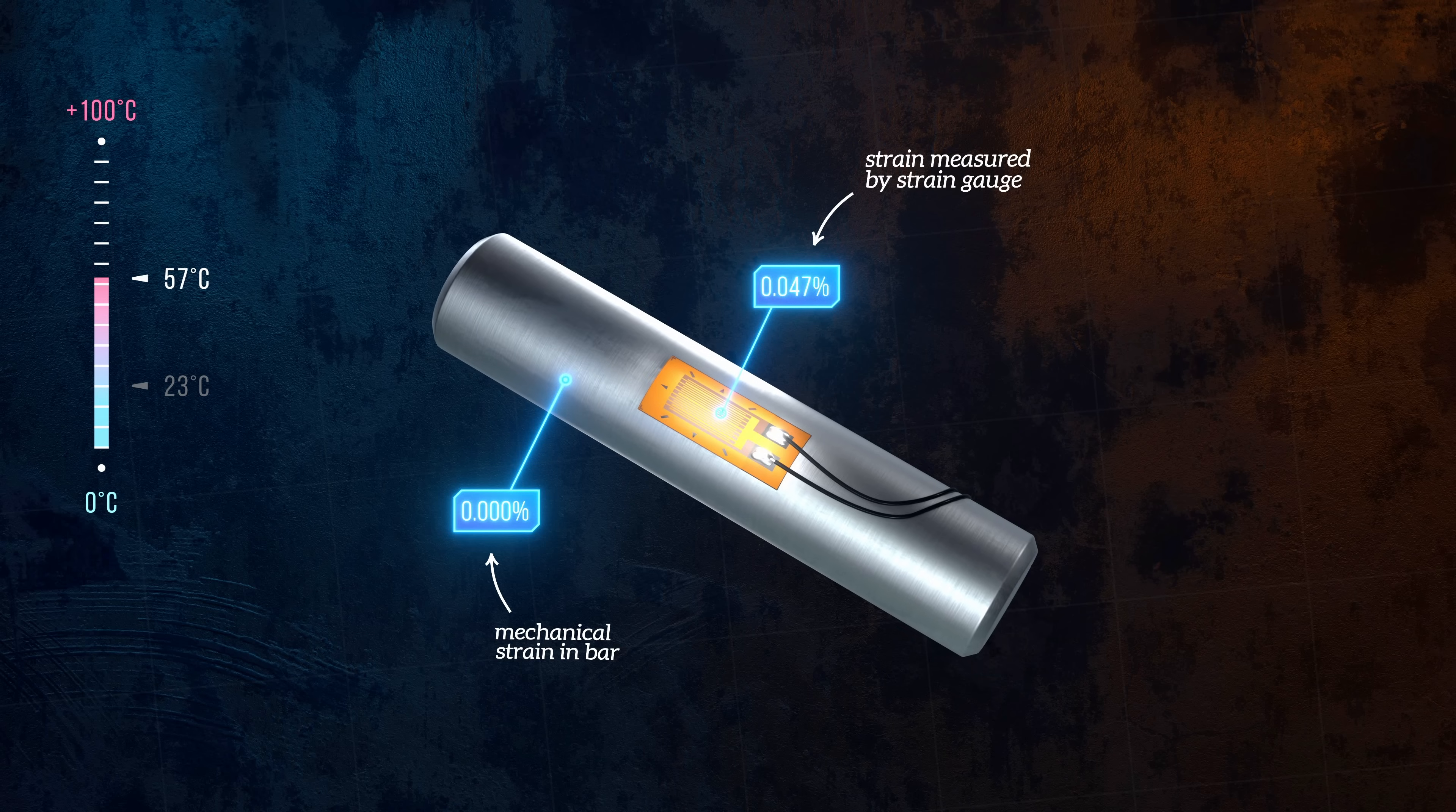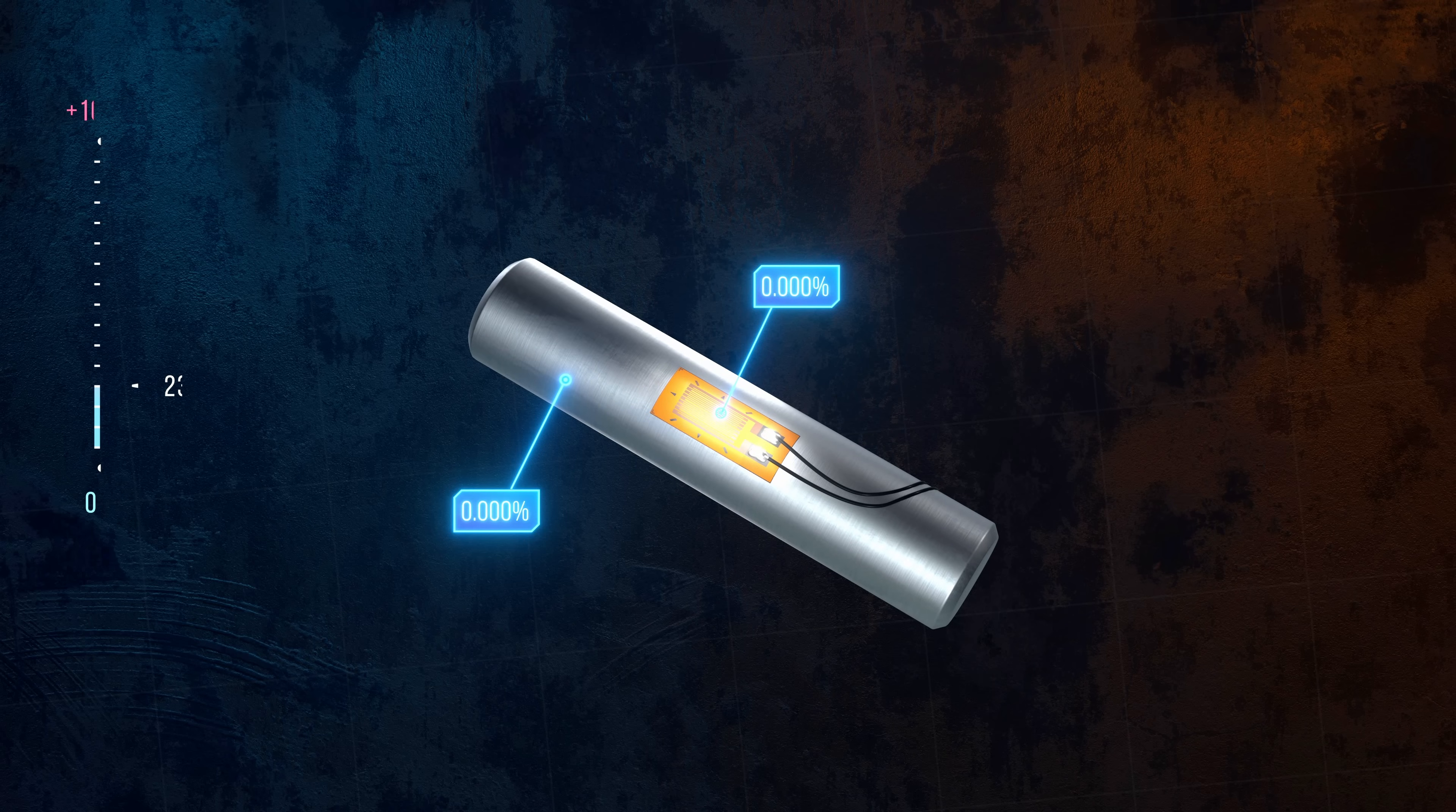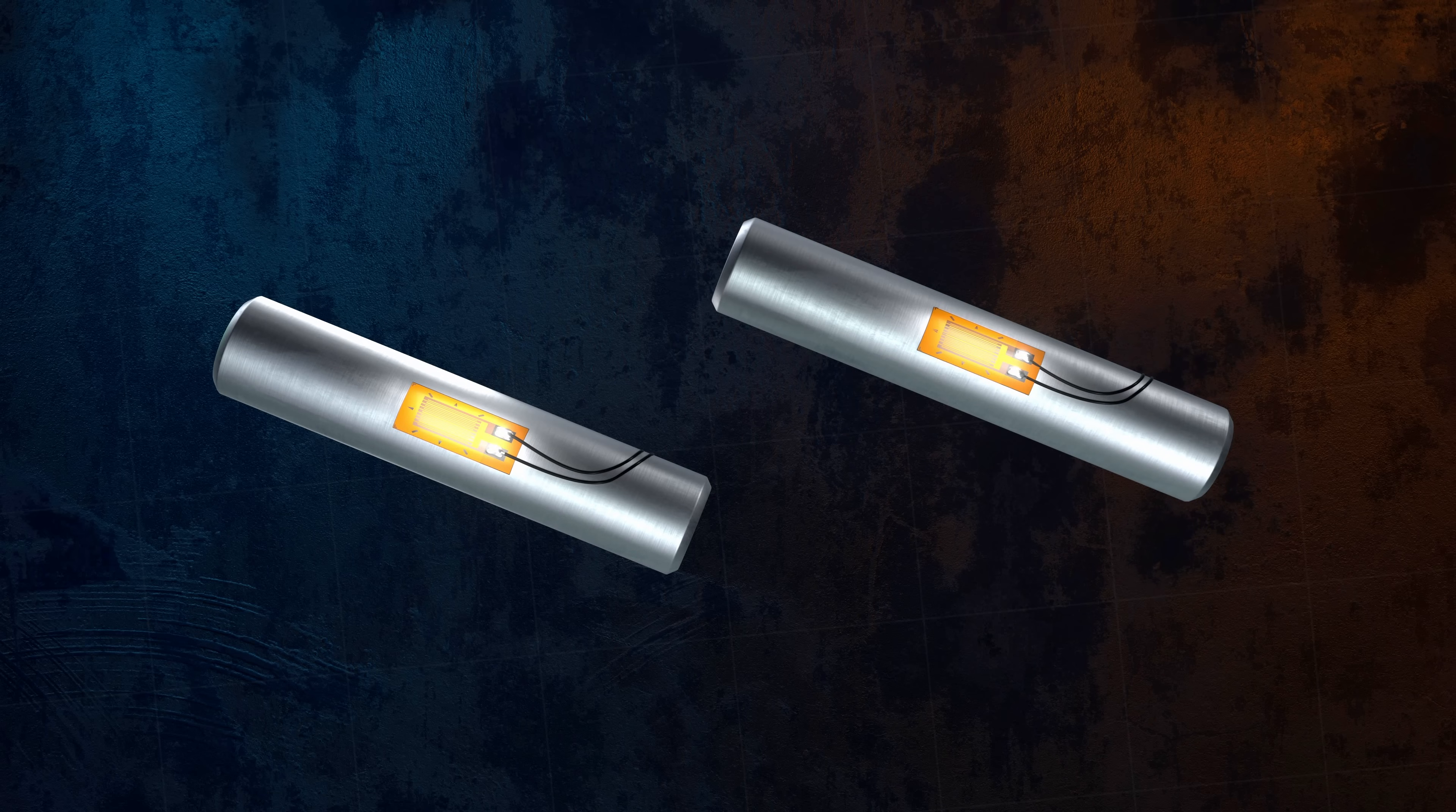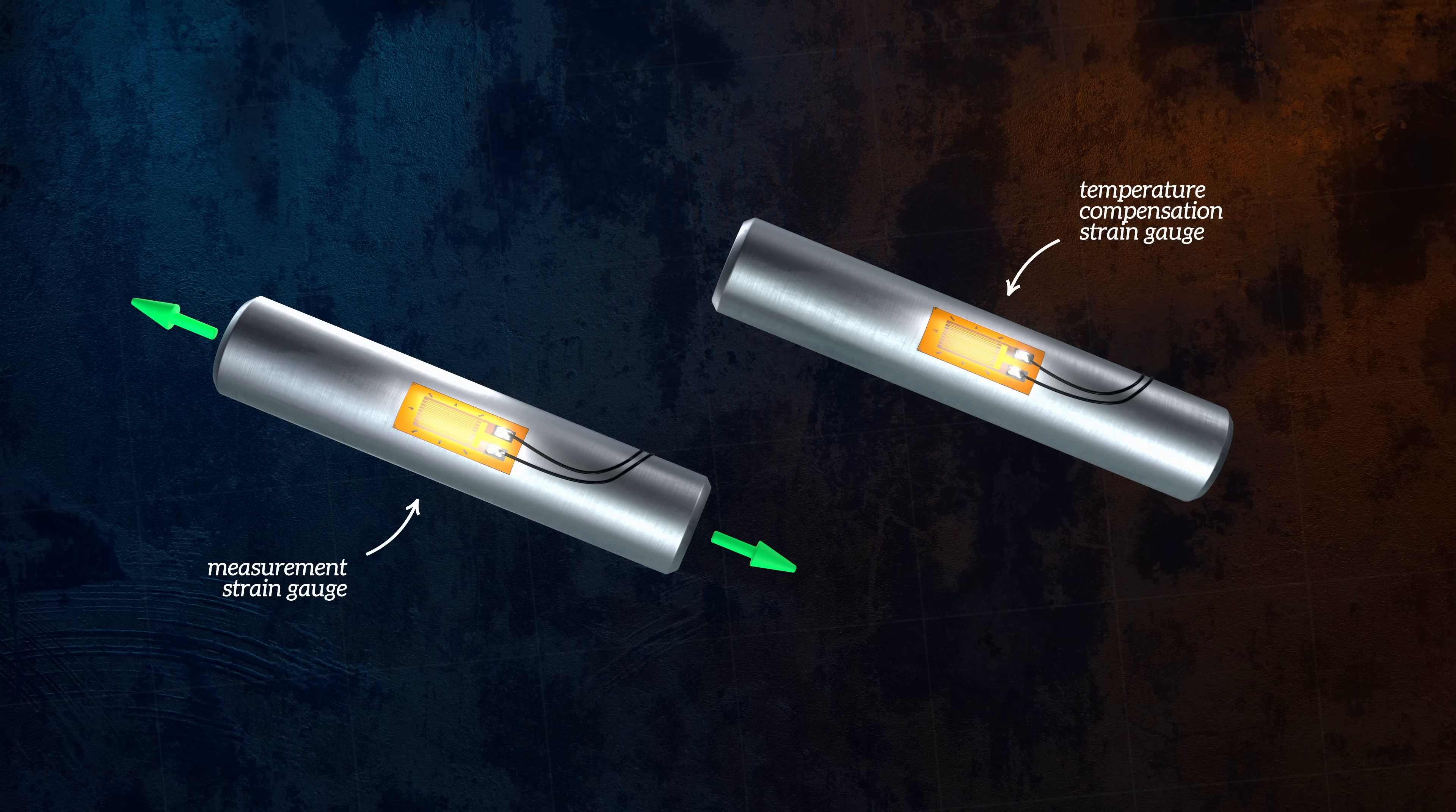Active compensation uses a second dummy strain gauge to compensate for thermal expansion. It's placed either in an unstressed region of the object being measured, or on a reference part that will experience the same level of thermal expansion, but without any applied loads. Both strain gauges are used in a half-bridge circuit, which cancels out the effects of thermal expansion.